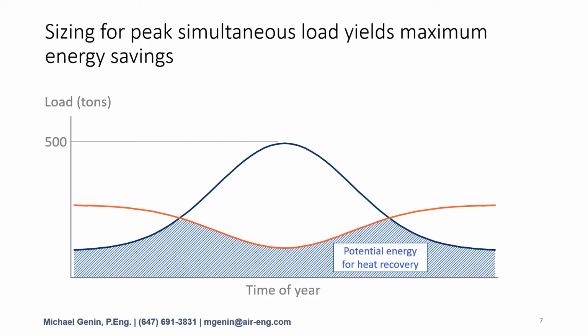This shaded blue region represents the simultaneous load. This is the total available energy for heat recovery. The most energy efficient case, or if we're looking for the largest greenhouse gas reductions, would be to size the chiller for the peak simultaneous load, 200 tons in this example.